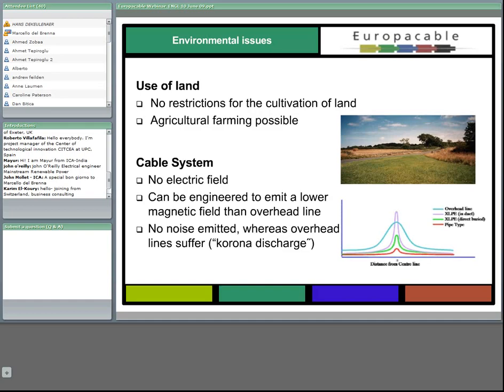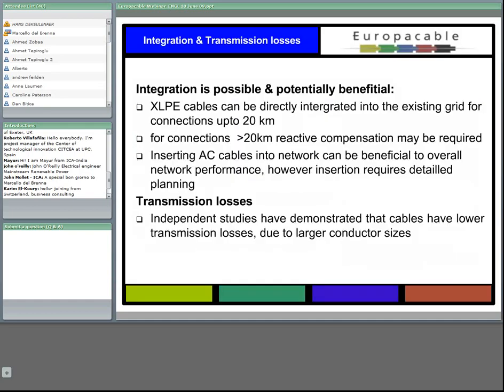The integration of cables in the transmission system. There is no basic problem to introduce XLPE cables in the transmission system. Yes, the cables have introduced capacitance in the overall system. They are not inductive, they are capacitive, which may reduce the length, the maximum length which can be used depending on the voltage, and probably at 400 kV every 20-30 kilometers reactive compensation may be needed.